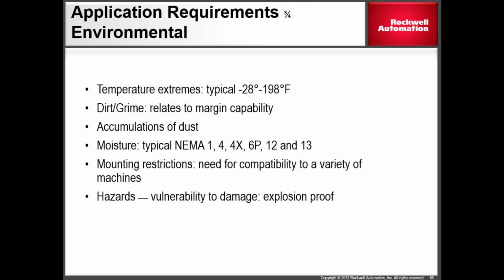Dirt and grime, that relates to the margin capability, how much light's going to get back, how often you need to clean that sensor. The accumulation of dust on it, if it's a real dusty environment, am I going to have to make it a standard operating procedure to clean it every hour or every shift, every week? It just depends on the environment. Moisture, NEMA 1, 4, 4X, 6P, 12 or 13. Now there's IP ratings, IP69 for almost a real heavy washdown rating.